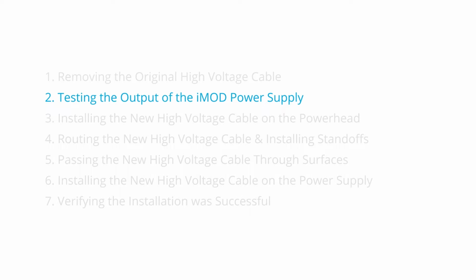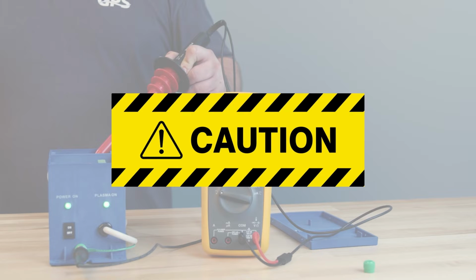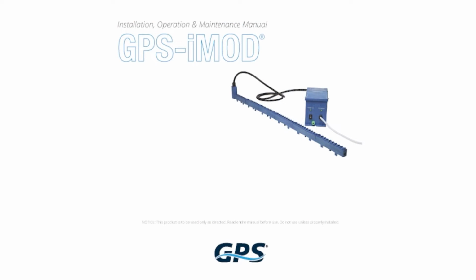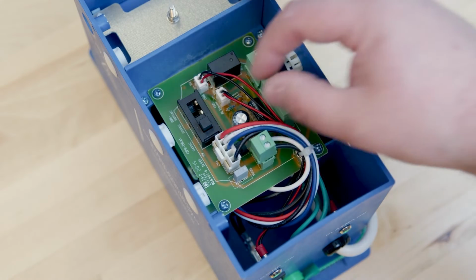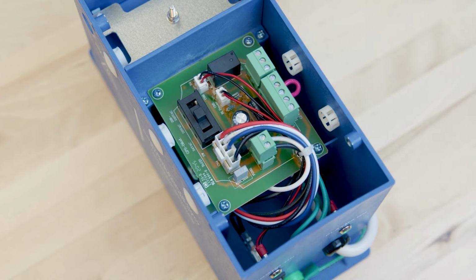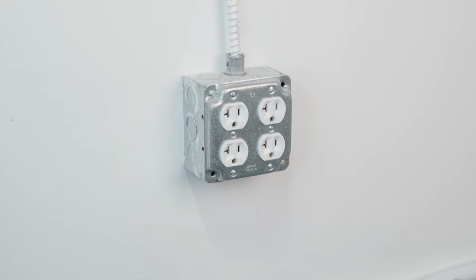Step 2. Testing the output of the iMOD power supply. If you do not have a high voltage probe, you may skip this step. Use caution when checking the voltage on the GPS iMOD power supply, as it produces high voltage which can be dangerous if appropriate safety measures are not taken. Ensure that all the high voltage cables have been removed from the power supply before powering on the device. If you are installing a new power supply, refer to the IOM. Ensure the voltage selector switch is set to the proper voltage also referenced in the IOM.